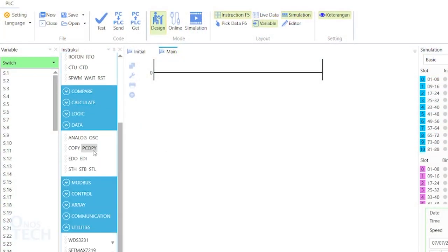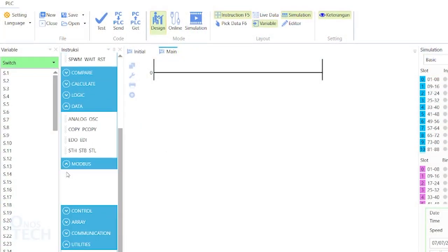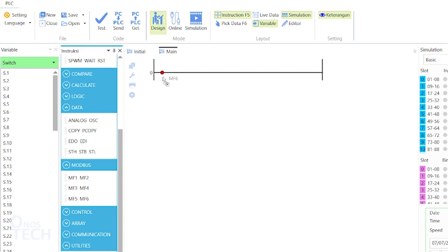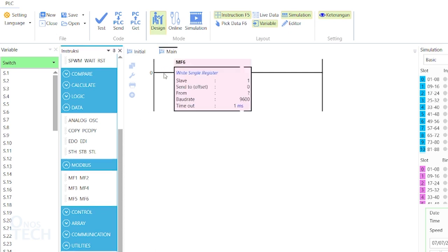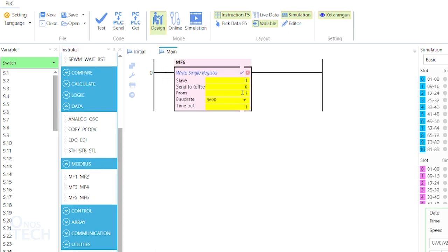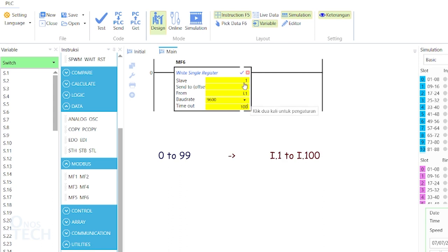MF6 is the Modbus function number 6 for writing to a holding register in a Modbus slave. The offset value from 0 to 99 as in MF3 corresponds to I.1 to I.100 in the slave PLC.